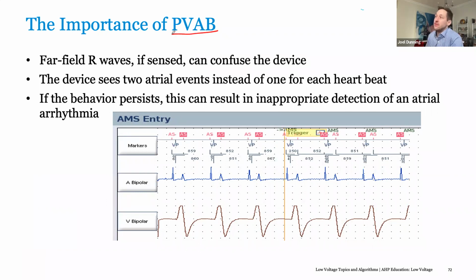Next, that brings us to PVAB. So that's your post-ventricular atrial blanking. So basically this is actually when the device is blind after a ventricular event. If you've inappropriately programmed your PVAB, what you may see occurring, like in this case, is double counting of atrial, or you'll basically see double counting because you'll be counting the ventricular signal on the atrial channel.